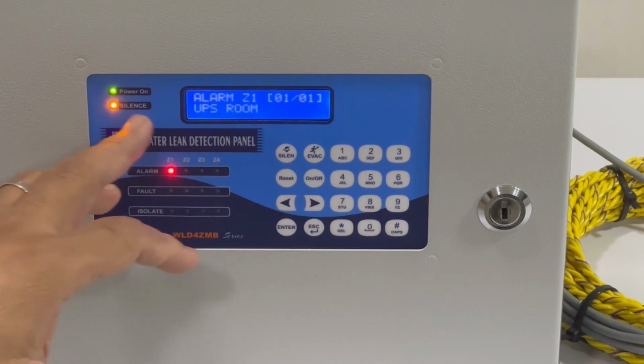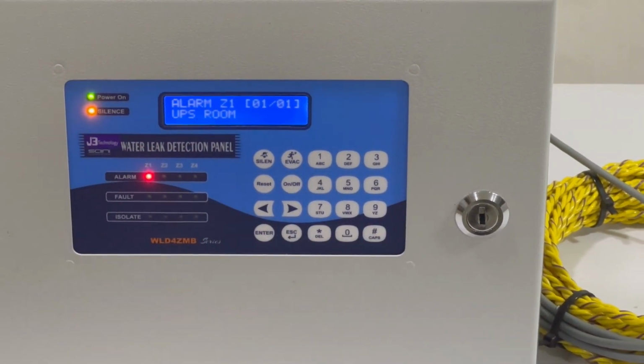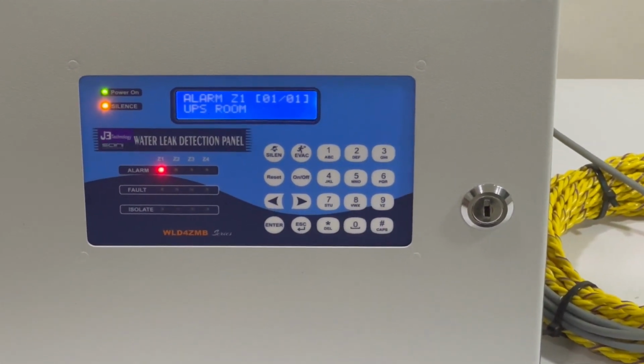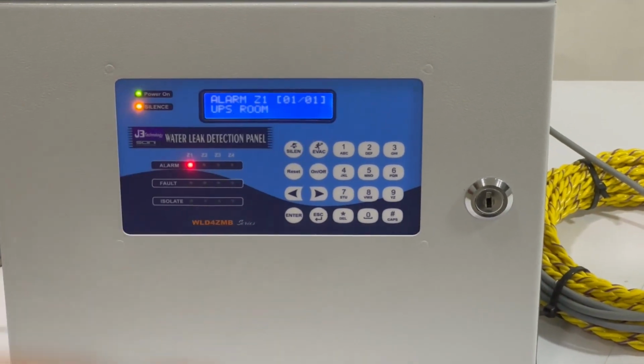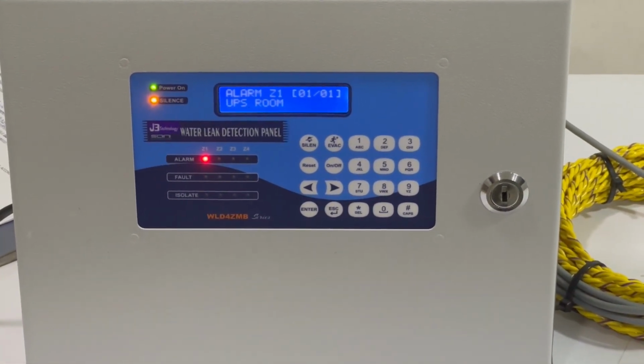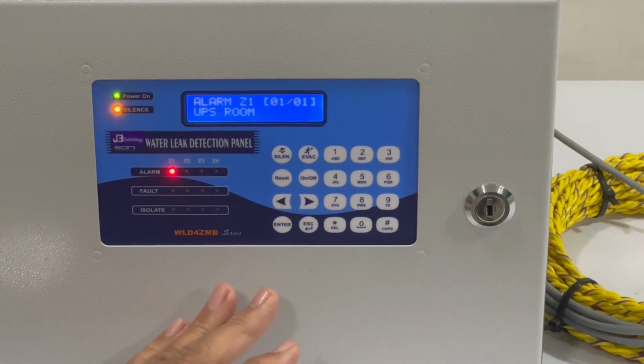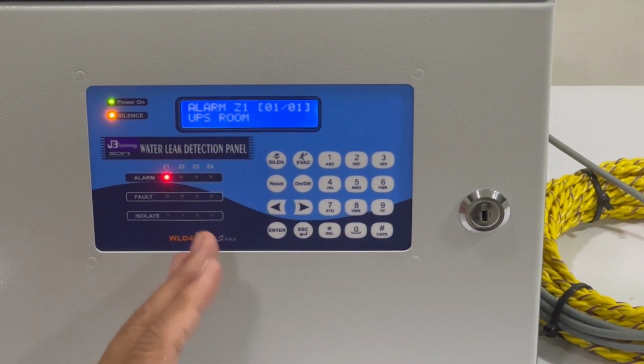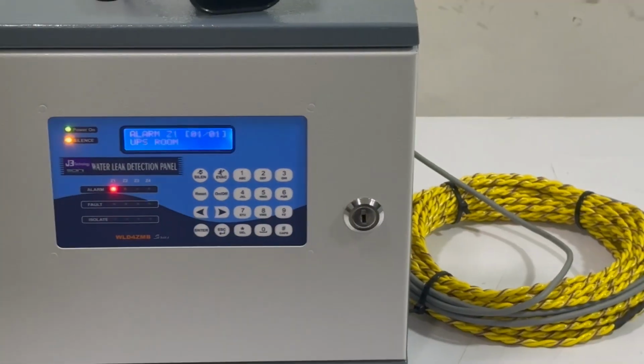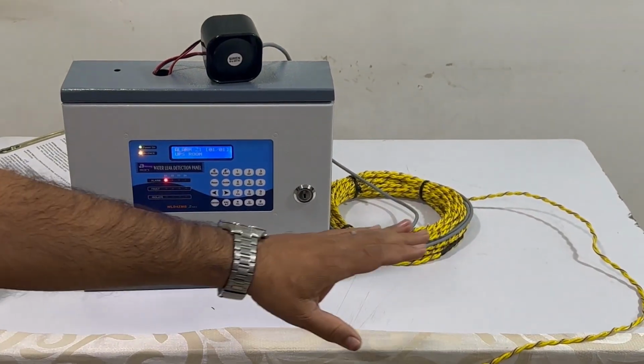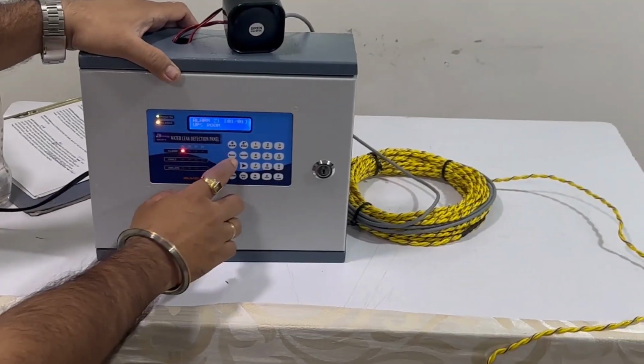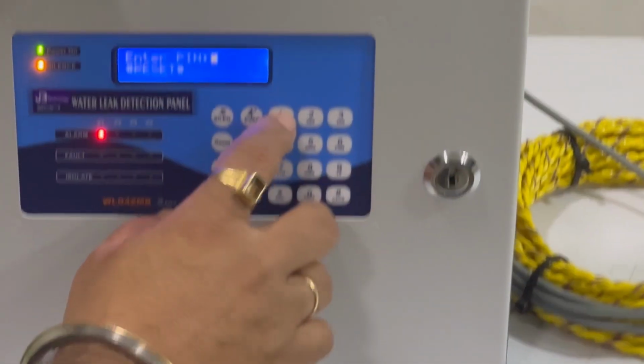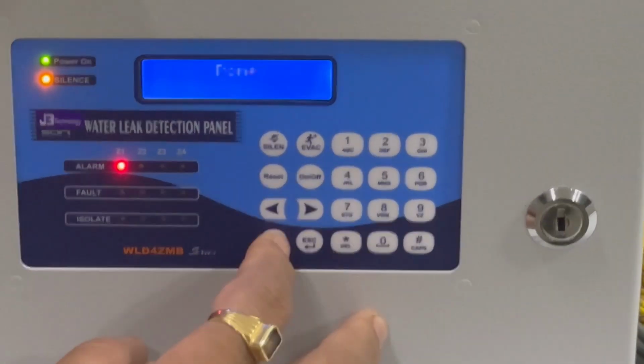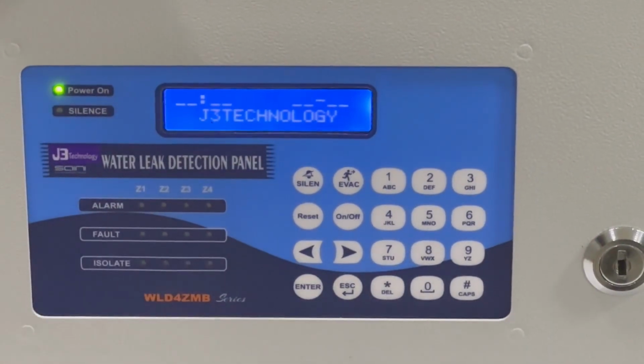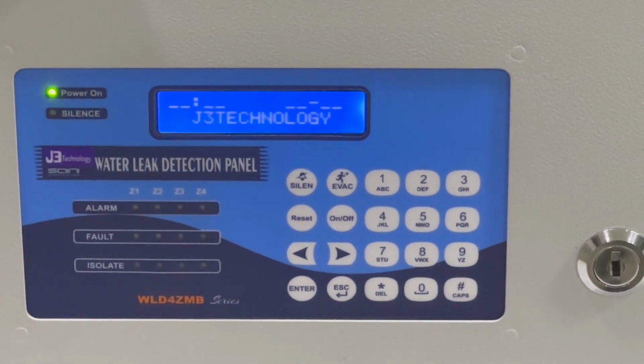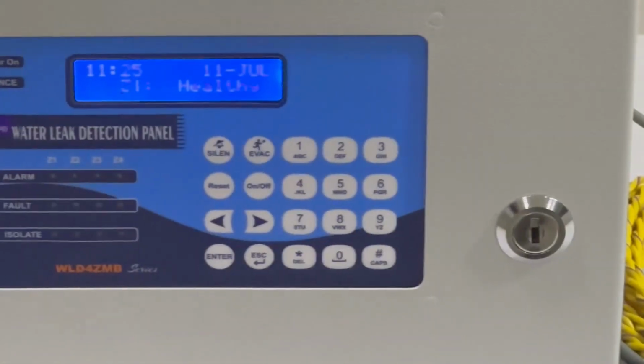Okay, guys. Now you can check why the alarm came and where the water has arrived. By silencing the alarm, you can go to the field and check where the water is. My reason for showing this is that the high sensitivity is high for normal; by touching with a wet hand, the alarm is generated. Now you can reset the panel again. 1, 2, 3, 4, and okay, the panel got reset. Now see, the alarm has gone.